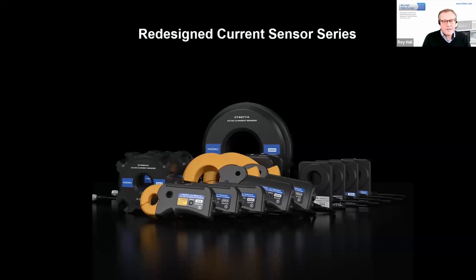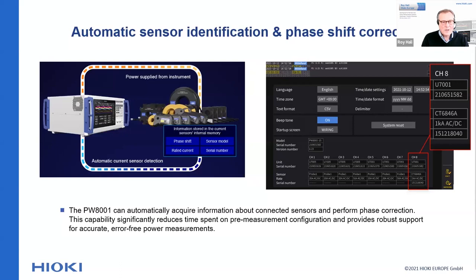As already mentioned, the current sensors are an essential part of accurate power measurement. Together with the PW8001, Hioki is introducing a range of new current sensors. The memory inside the sensors makes automatic identification of the current sensor and automatic phase shift correction possible. This feature reduces the setup time and minimizes the chance of measurement errors due to phase shift error and scaling errors. For applications where traceability is important, it is interesting to know that the serial number of the current sensor can be logged in the measurement file as well.